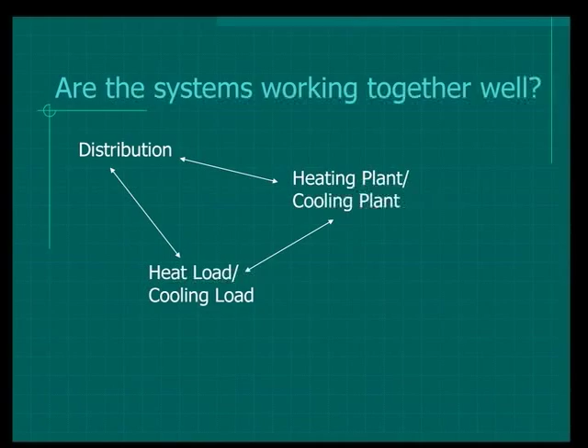And certainly the other factor is the house itself and what the heat load is. So if my ductwork is smaller than my furnace, what are my choices? If we want to get this system matched up, we need to ask: what's the heat load on the house? Is the furnace bigger than the house, or is the furnace just right? If the furnace is bigger than the house, we size the furnace down so the furnace matches the ductwork matches the house. Problem solved. If the furnace is the right size for the house, then we've got to bring the ductwork up in size to make that work efficiently. Not a real easy retrofit in a lot of situations.